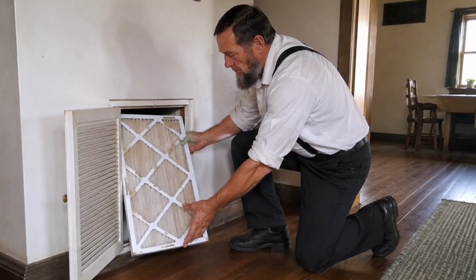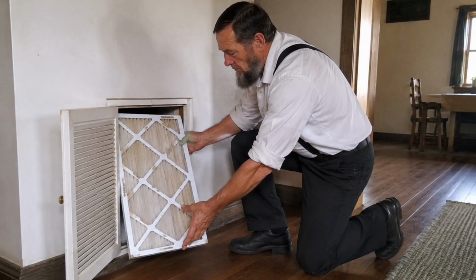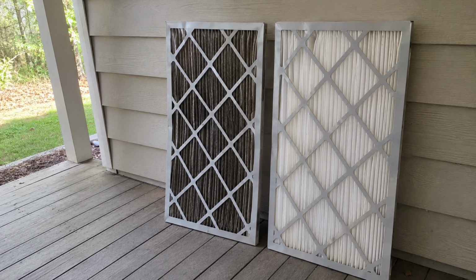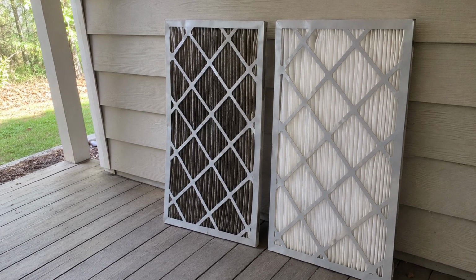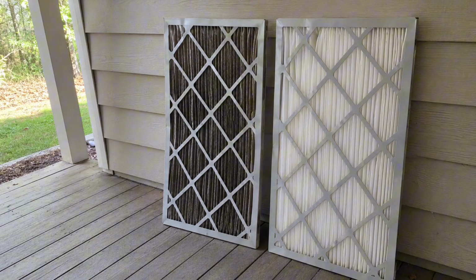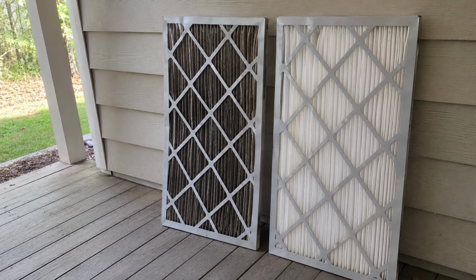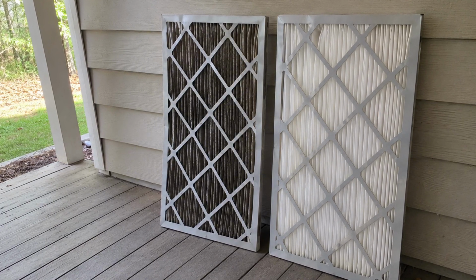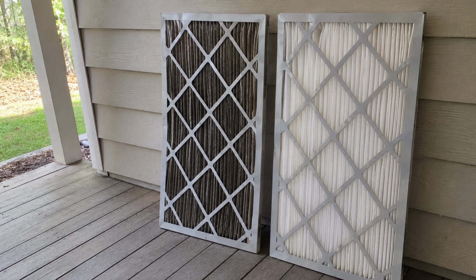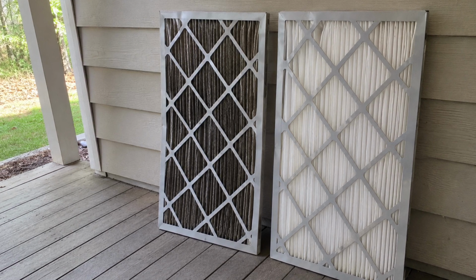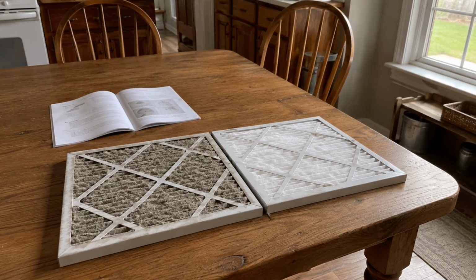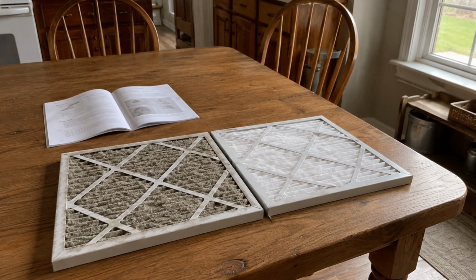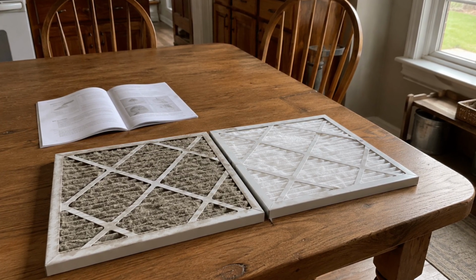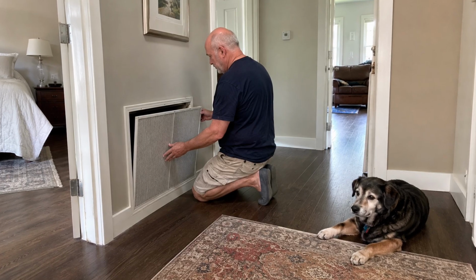That filter normally sits somewhere in the return side of the system, which means the system's air must pass through it before reaching the blower and coil. It is not a little accessory. A filter loaded with dust adds resistance just as surely as a blocked grill does. Use the size and filter type your equipment is meant to accept. Follow the equipment and filter instructions for replacement.